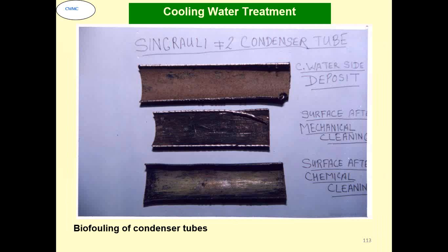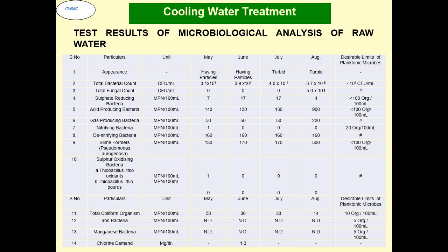Typical effect of the biofouling. Typical test result of a station where the problem was biofouling related. It was a once-through system, and at different time periods, when we analyzed, the microbiological characteristics were very high, much beyond the acceptable levels, and because of that the condenser vacuum was affected, because the station was not using any chlorine or any other microbiological treatment, since it was a large once-through system. But when the problem started, they were advised to go in for chlorine dosing, and since then the problem has been under control.